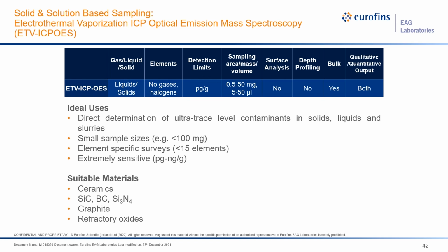It is proven to work very well with ceramics, silicon carbide, graphite, and refractory oxides. So those materials that are traditionally difficult to digest or analyze by typical ICP-OES or MS techniques.